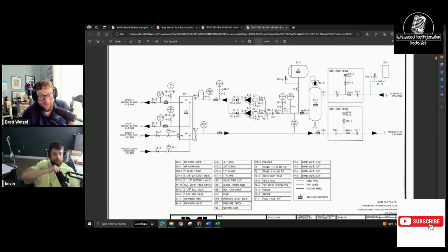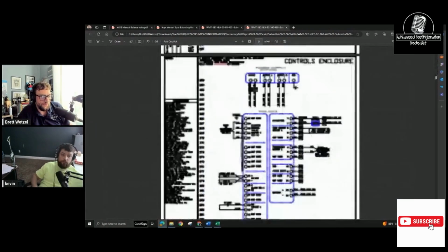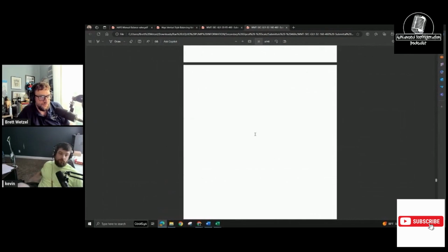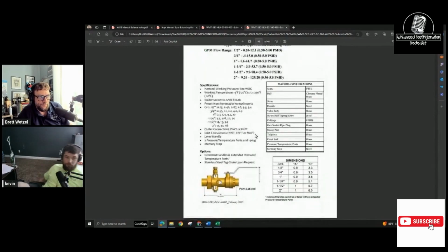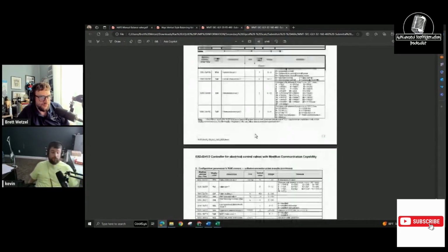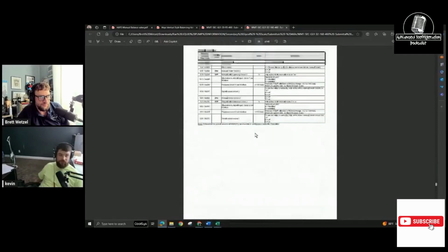What kind of brazed exchangers are they? I don't know. Because look, so you have circuit 2 liquid, and then technically this is circuit 2 suction, circuit 1. But yeah, you've got to really pay attention because the ones that Zero Zone uses are cross piped. That's why I'm looking right now. That'll really screw you up when you're piping it. You really got to pay attention.